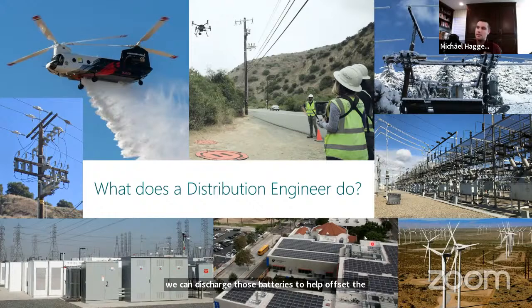Here in the middle, you can see a commercial solar installation on top of one of our local schools. As distribution engineers, we have to look at all of these and commission the projects to make sure all of the gear they're implementing, their switch gear, their inverter settings, their relay protection settings, is compliant with our standards. We can't just have people hooking their stuff up to the grid. That doesn't make for a very consistent application.